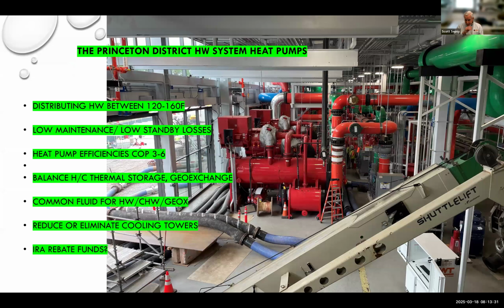This is a picture of the heat pumps installed in the Tiger plant. Out of the plant, we distribute hot water between 120 to 160. The new system has low maintenance and low standby losses, very good insulation system. The heat pump coefficients vary, typically between 3 and 6. We try to balance the heating and cooling using the thermal storage tanks and the geo-exchange system. The storage tanks are for daily or weekly use, and the geo-exchange is more of a seasonal battery.